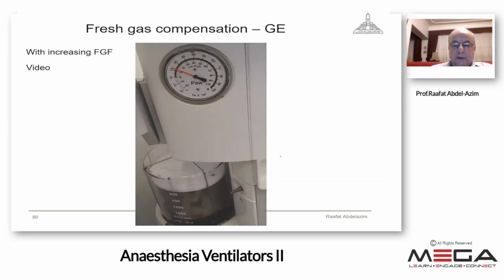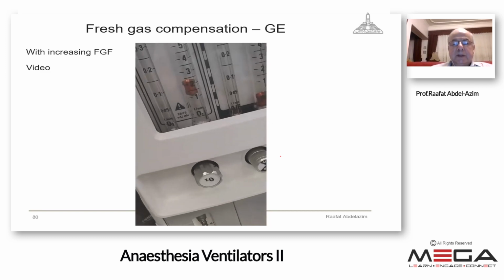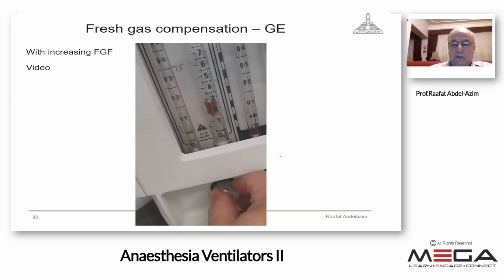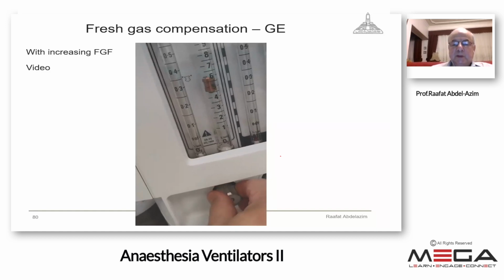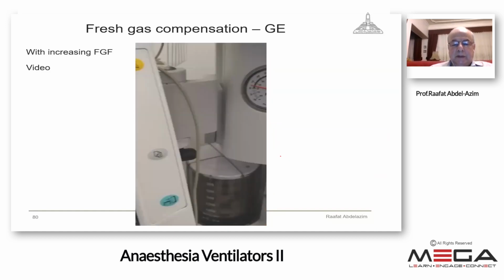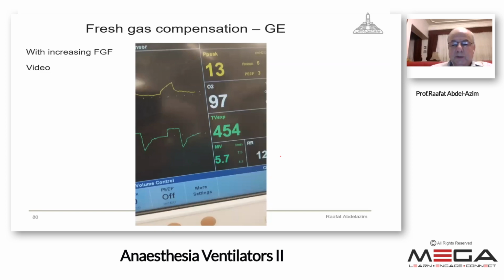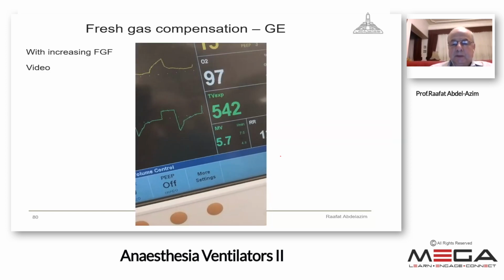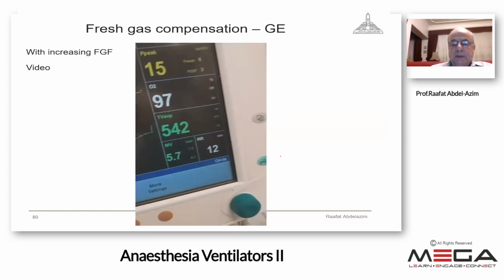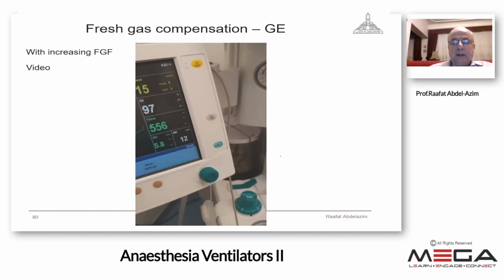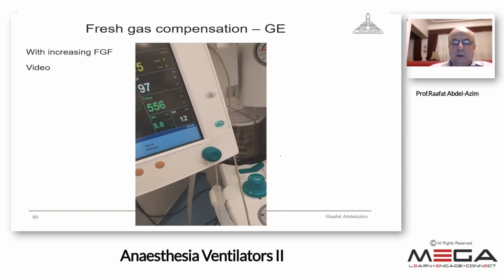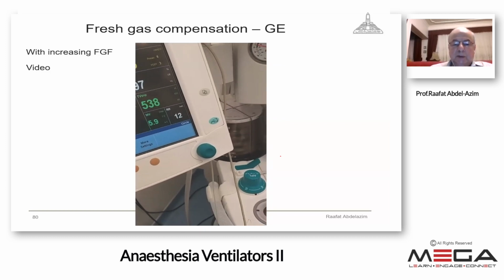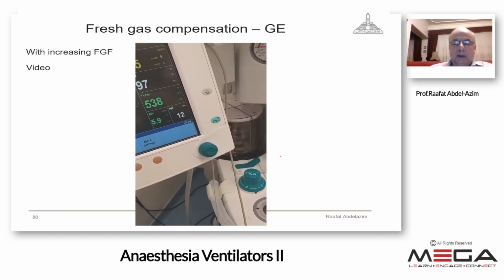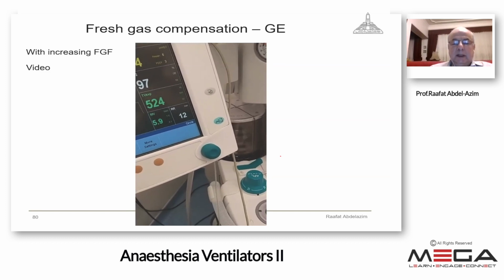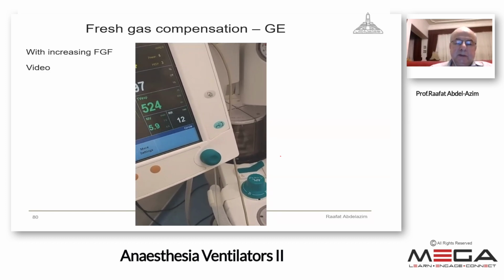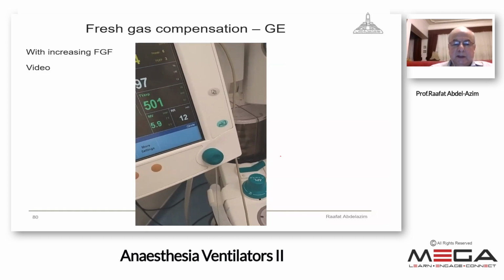The ventilator is going down. Here, the fresh gas flow is 2 liters. If we increase the fresh gas flow from 2 liters to 6 liters, this will of course add to the delivered tidal volume. And now you see it will go up. It is now 540. The fresh gas compensation will be activated. It's going up again, then the fresh gas compensation will work to let it go down and be near the preset tidal volume again. It is only 3, 4, 5 cycles going down.